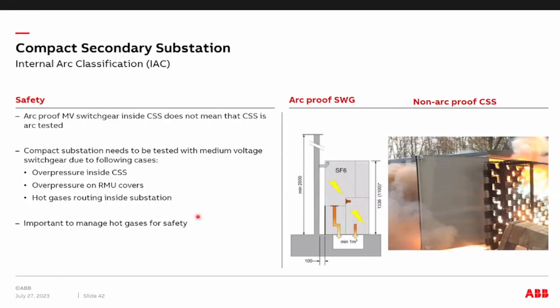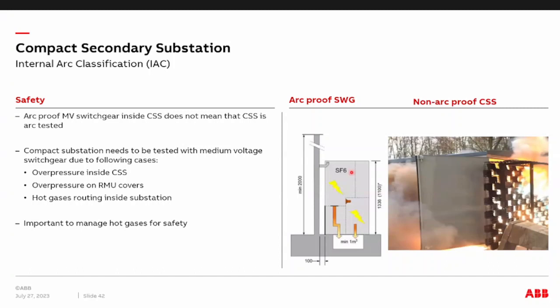Compact substation needs to be tested with medium voltage switchgear due to the following cases: sometimes we have overpressure inside CSS, overpressure on RMU covers, and hot gases routing inside the substation. That's why the type testing by ABB actually considers or includes the RMU or the switchgear inside the CSS. It's very important that the hot gases are managed, of course, for safety purposes.